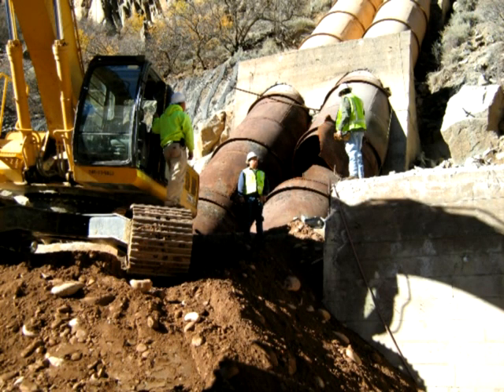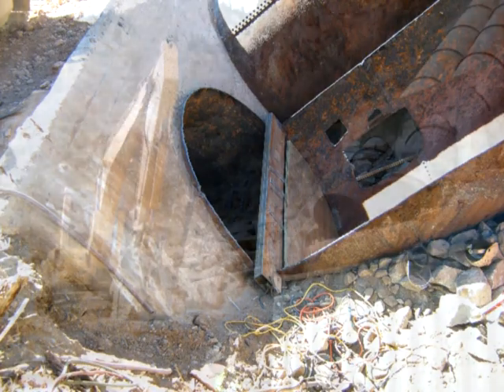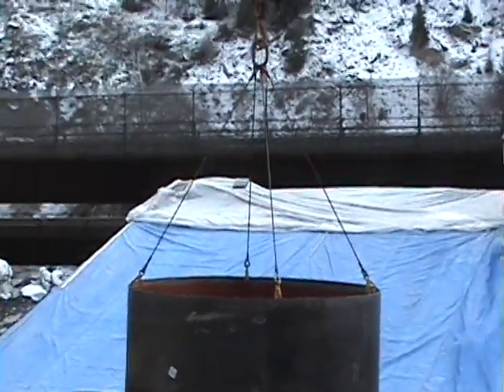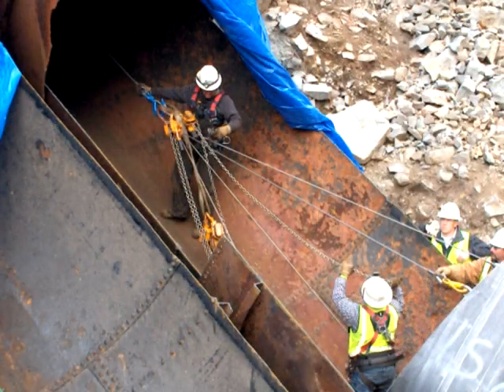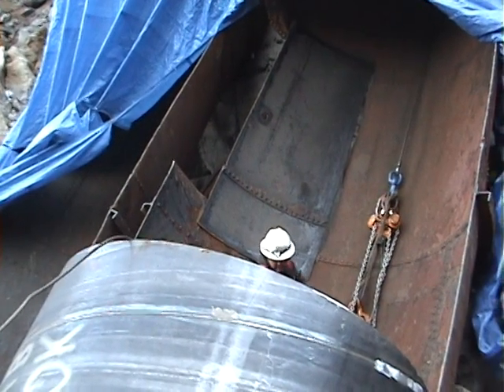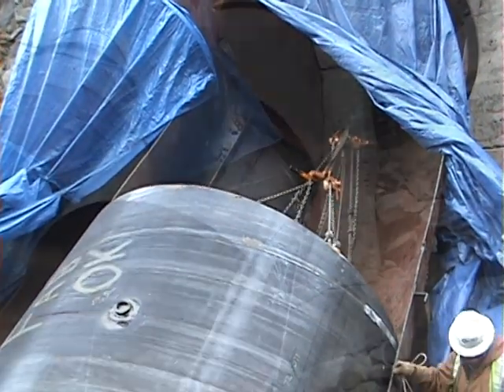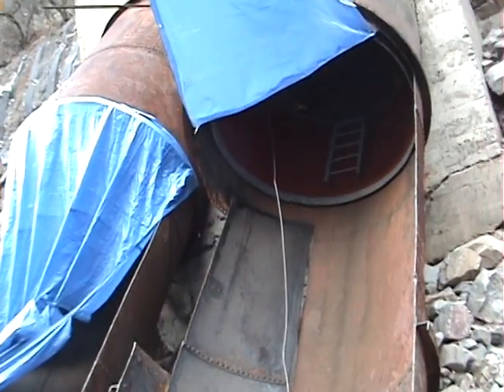Down below, the first step was to make a bigger hole. The damaged pipe was removed and we cut an opening in each penstock large enough for the new pipe sections. The pipe is moved one section at a time to the bottom of a penstock and secured with four lines to a harness, which is connected to the winch. Once the section is in position, the winch pulls it into the old penstock — and up, and up, and up.